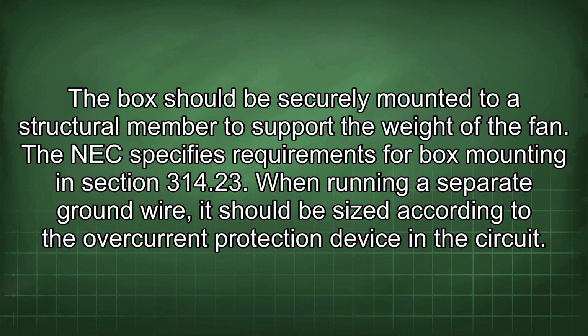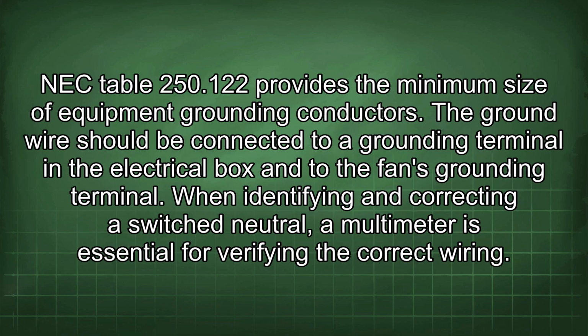The NEC specifies requirements for box mounting in Section 314.23. When running a separate ground wire, it should be sized according to the overcurrent protection device in this circuit. NEC Table 250.122 provides the minimum size of equipment grounding conductors. The ground wire should be connected to a grounding terminal in the electrical box and to the fan's grounding terminal.